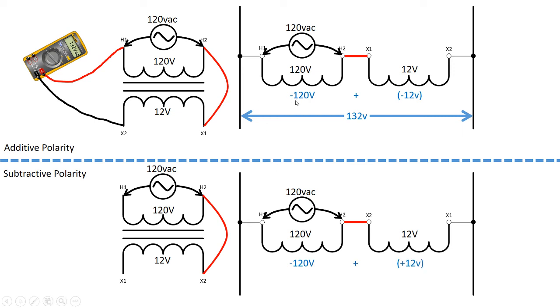So previously in our additive, we had negative 120 plus negative 12 gave us a higher overall result. But if we look now at our subtractive down here, negative 120 plus positive 12, this will actually give me a less than we started with voltage, and we should see somewhere around 108 volts on this connection.